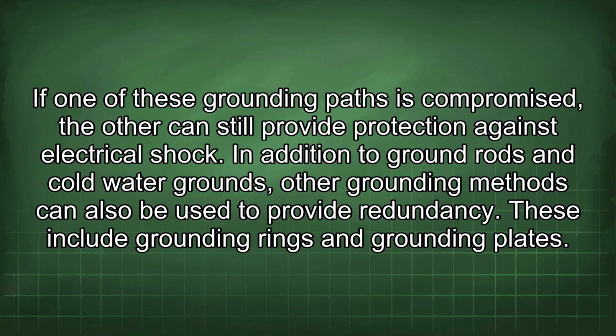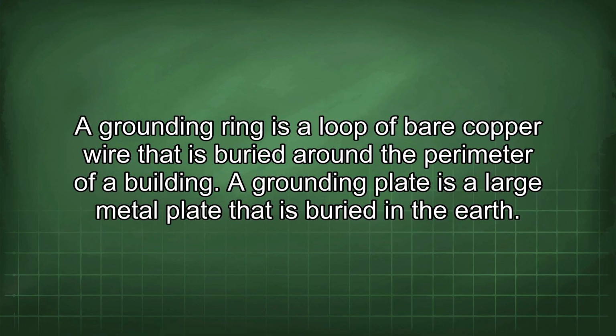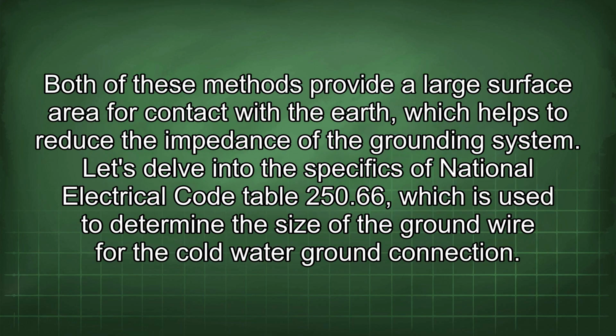In addition to ground rods and cold water grounds, other grounding methods can also be used to provide redundancy. These include grounding rings and grounding plates. A grounding ring is a loop of bare copper wire that is buried around the perimeter of a building. A grounding plate is a large metal plate that is buried in the earth. Both of these methods provide a large surface area for contact with the earth, which helps to reduce the impedance of the grounding system.